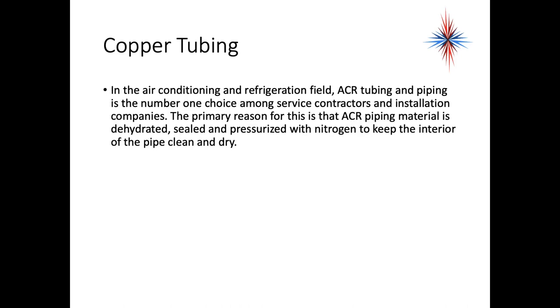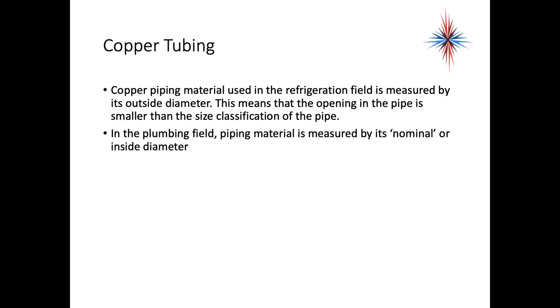In the air conditioning and refrigeration field, ACR tubing and piping is the number one choice among service contractors and installation companies. The primary reason for this is that ACR piping material is dehydrated, sealed, and pressurized with nitrogen to keep the interior of the pipe clean and dry.